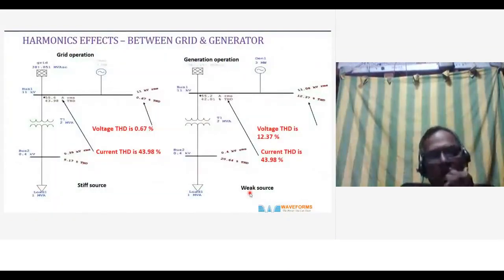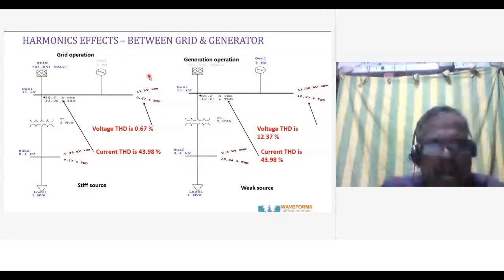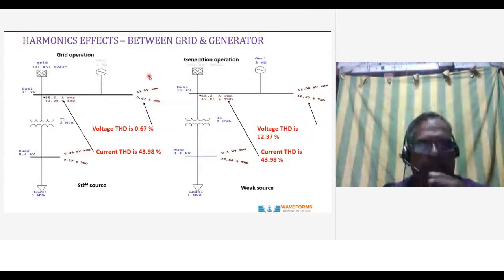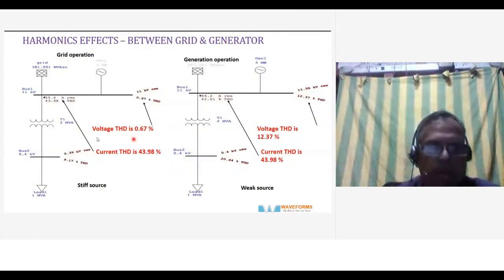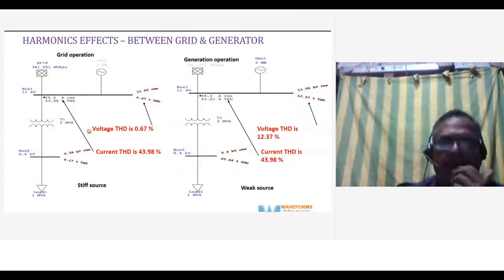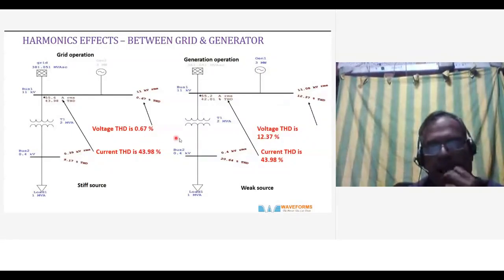So now to understand the THD, there are two things. Mostly all plants use a generator and the grid supply. Most industries have generators. So there is a difference when you have harmonics. The voltage distortion in the grid, you notice that it doesn't get distorted much. At a current THD of 43.98, the voltage distortion is 0.6.